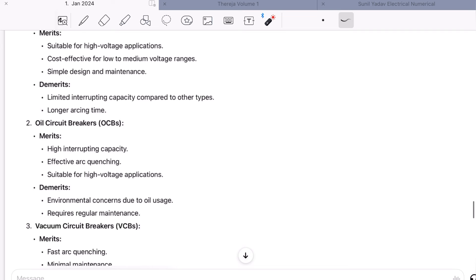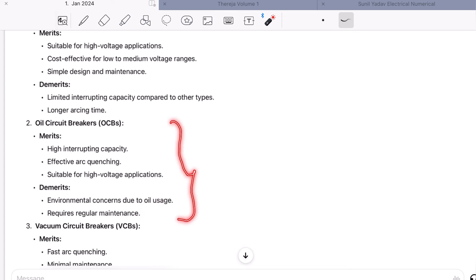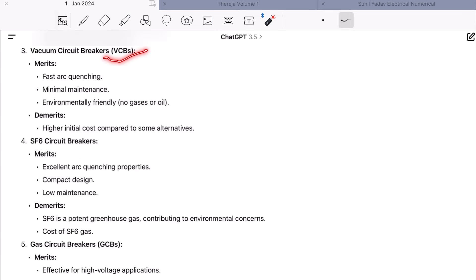ACB merits: suitable for high voltage system, cost effective for low to medium voltage range, simple design and maintenance. Demerits: limited interrupting capacity and long arcing time. The next type is oil circuit breaker. Merit: high interrupting capacity, effective arc quenching, suitable for high voltage application. Demerits: environmental concerns due to oil use, regular maintenance required. Note that oil circuit breakers are usually not used in marine systems, so you can remove this from your answer. Now, the vacuum circuit breaker, which is mostly used in the marine field for high voltage systems where voltage is greater than 1000 volts.